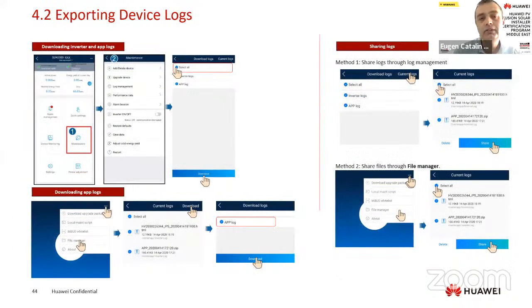Device logs are important for us from service. When we need to check a problem of the inverter, to give you some recommendation or check if it is a warranty case, we need a log file. So we can export the log file from the inverter directly from the maintenance, log management, and we can export the inverter logs. Your RAR archive will be saved automatically in your phone, or you can share it directly if you have set an email with us.